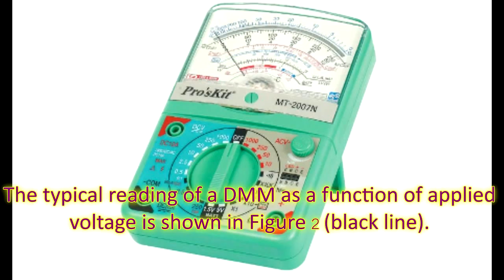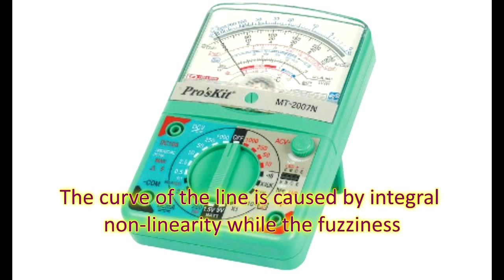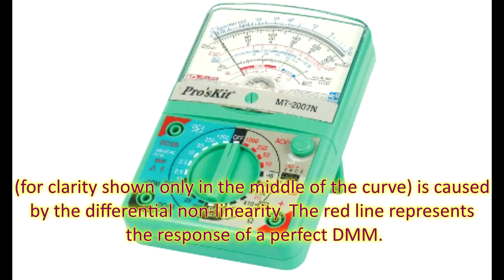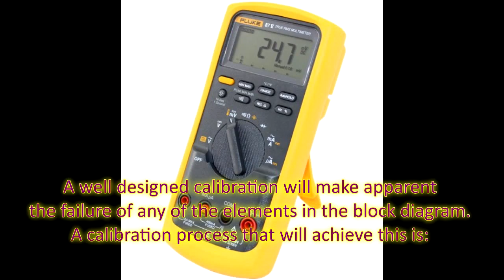The typical reading of a DMM as a function of applied voltage is shown in Figure 2, black line. The curve of the line is caused by integral nonlinearity, while the fuzziness, for clarity shown only in the middle of the curve, are caused by the differential nonlinearity. The red line represents the response of a perfect DMM. A well-designed calibration will make apparent the failure of any of the elements in the block diagram.